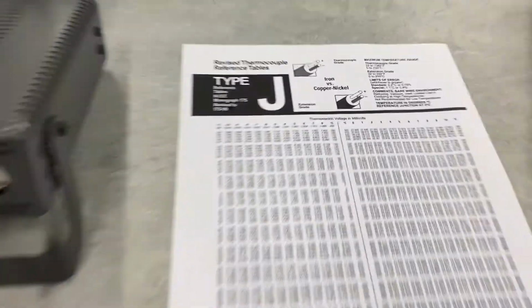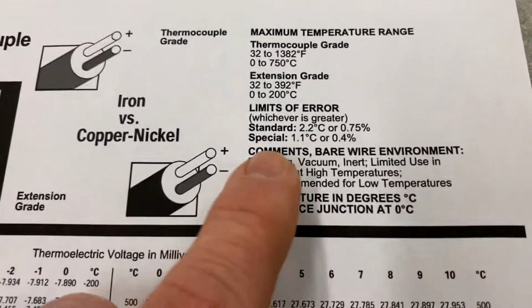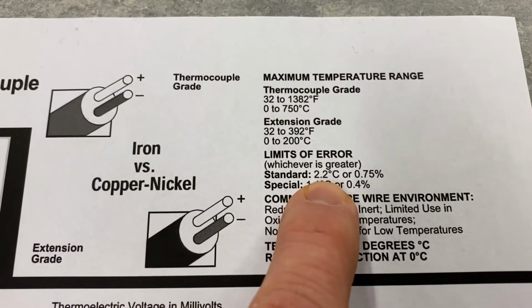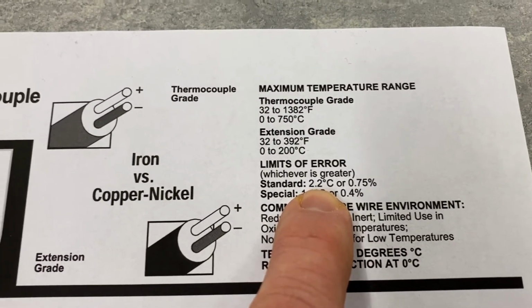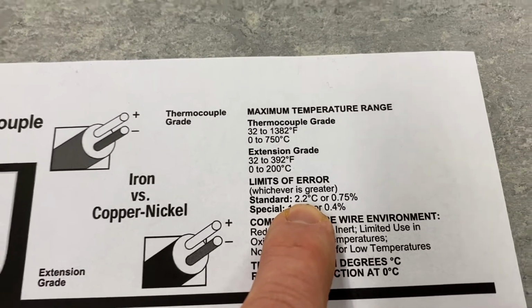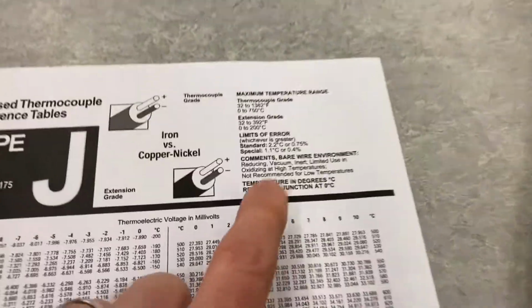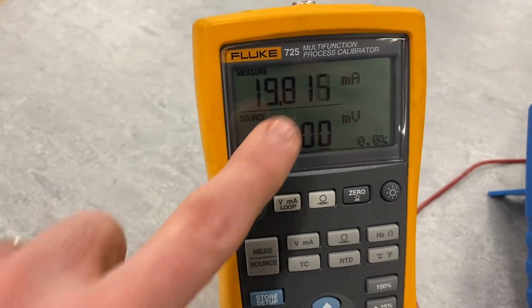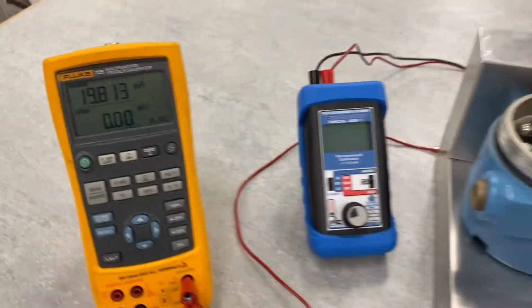The type J thermocouple right here. You can see if we're dealing with standard here, the limits of error is going to be plus or minus 2.2 degrees C here. So that equates to about 0.35 milliamps roughly in our range. And so we're within 0.2, so we're within that range. We're good to go on to the next step.